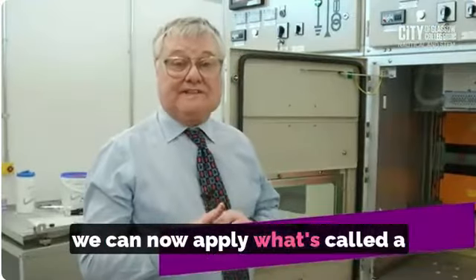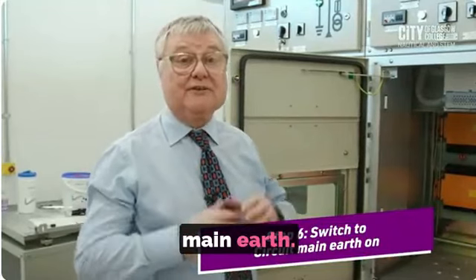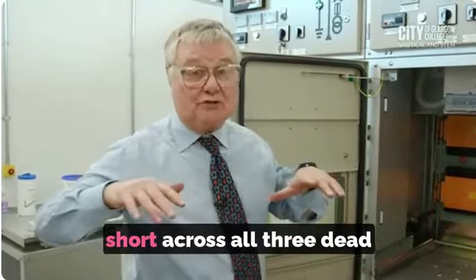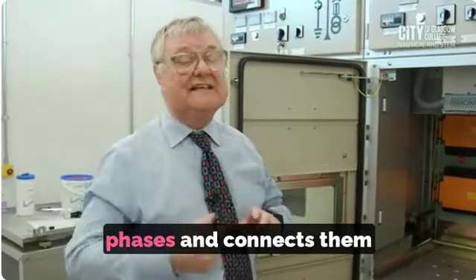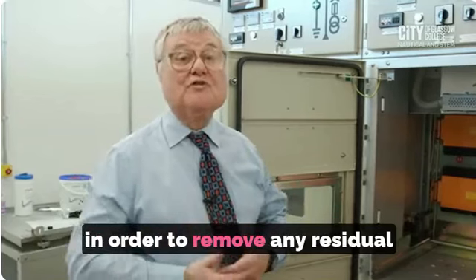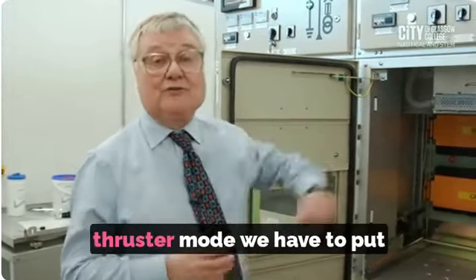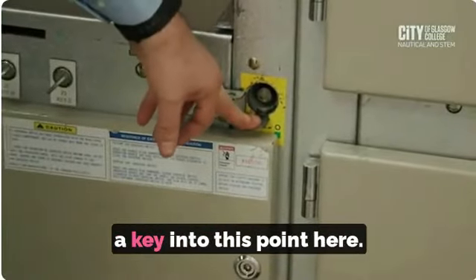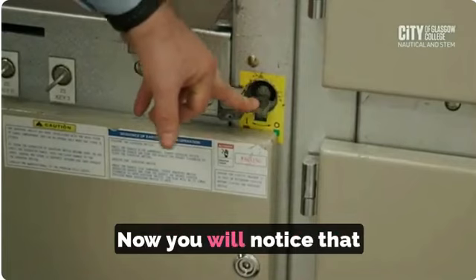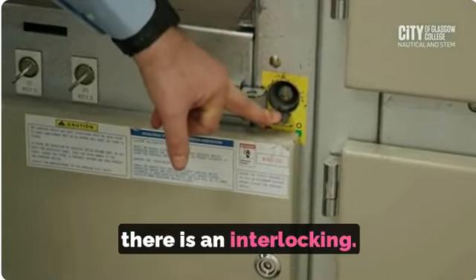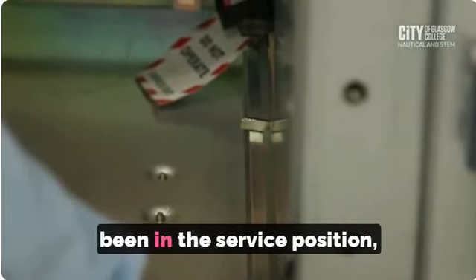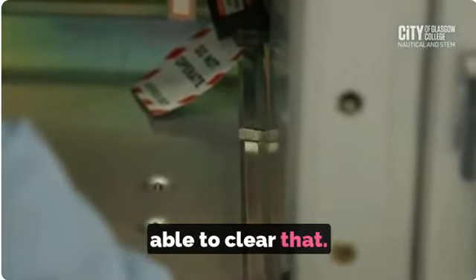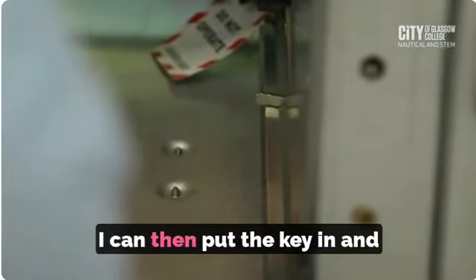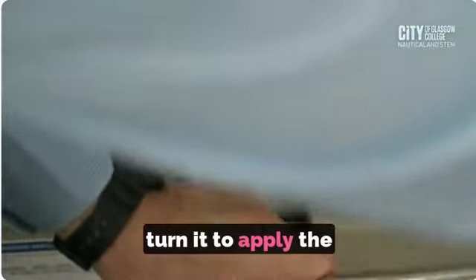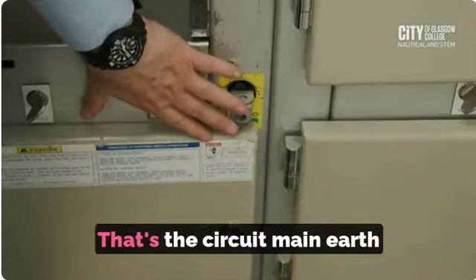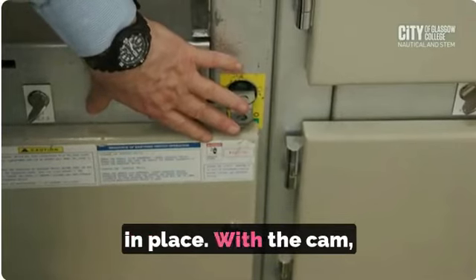We can now apply what's called the circuit main earth. The circuit main earth puts a dead short across all three dead phases and connects them down to earth in order to remove any residual voltage which may be in the bow thruster motor. We have to put a key into this point here. Now, you will notice that when I push this down, there is an interlock. If the circuit breaker had still been in the service position, I wouldn't have been able to clear that. When it's pushed down, I can then put the key in and turn it to apply the circuit main earth. That's the circuit main earth now applied, and it's locked in place with the key.